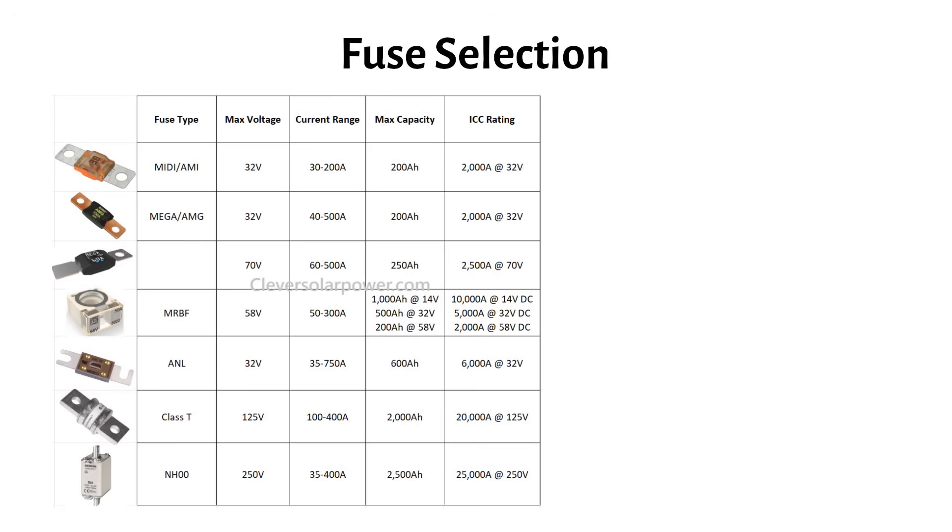Not all fuses are created equal. Here's the biggest mistake I see. People using mega fuses on 48 volt systems. Standard mega fuses are only rated for 32 volts maximum. If you're running a 48 volt system, you need a fuse that can handle at least 60 volts, like a 70 volt rated mega fuse, an MRBF, class T, NH00 fuse or a battery breaker. Using the wrong voltage rating is dangerous and can lead to catastrophic failure.